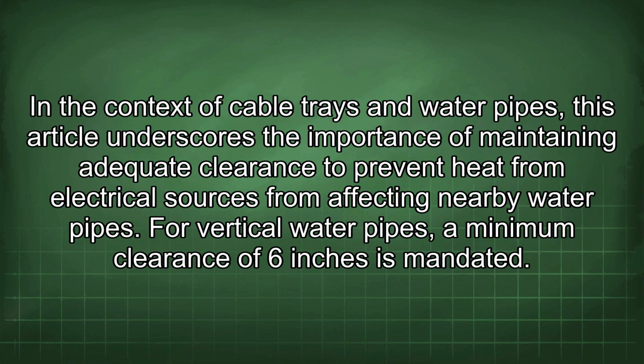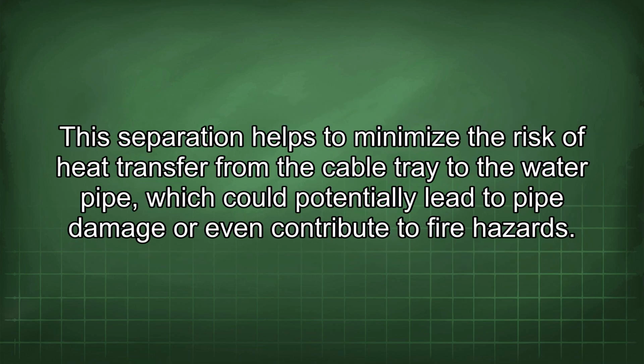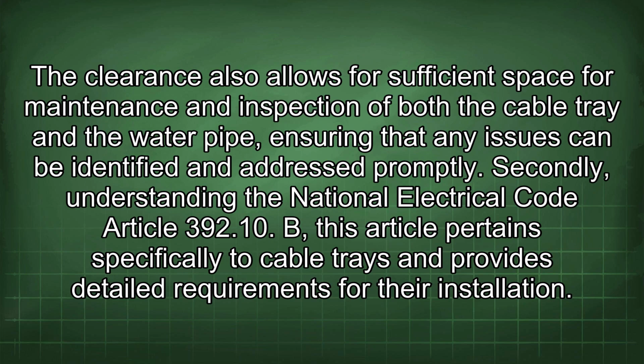In the context of cable trays and water pipes, this article underscores the importance of maintaining adequate clearance to prevent heat from electrical sources from affecting nearby water pipes. For vertical water pipes, a minimum clearance of 6 inches is mandated. This separation helps to minimize the risk of heat transfer from the cable tray to the water pipe, which could potentially lead to pipe damage or even contribute to fire hazards. The clearance also allows for sufficient space for maintenance and inspection of both the cable tray and the water pipe, ensuring that any issues can be identified and addressed promptly.